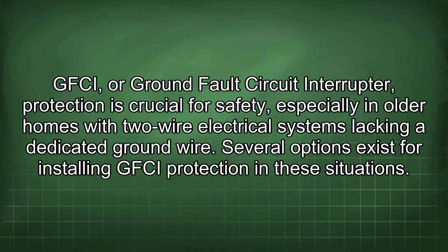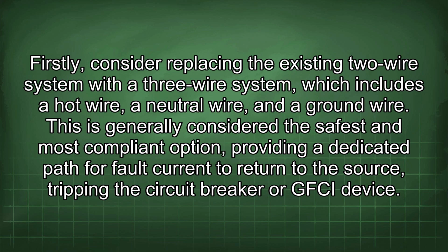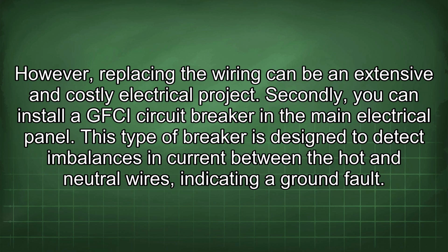GFCI, or ground fault circuit interrupter, protection is crucial for safety, especially in older homes with two-wire electrical systems lacking a dedicated ground wire. Several options exist for installing GFCI protection in these situations. Firstly, consider replacing the existing two-wire system with a three-wire system, which includes a hot wire, a neutral wire, and a ground wire. This is generally considered the safest and most compliant option, providing a dedicated path for fault current to return to the source, tripping the circuit breaker or GFCI device. However, replacing the wiring can be an extensive and costly electrical project.